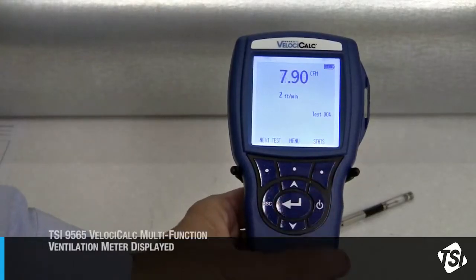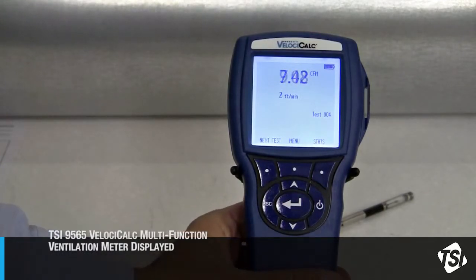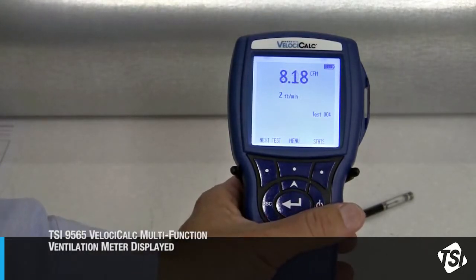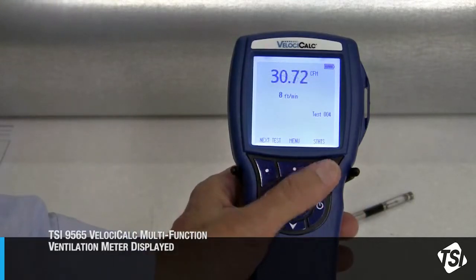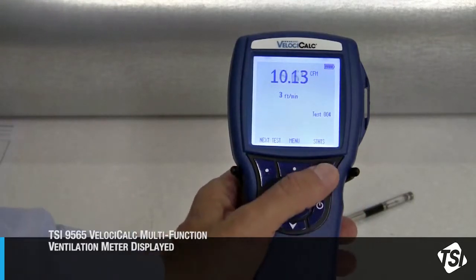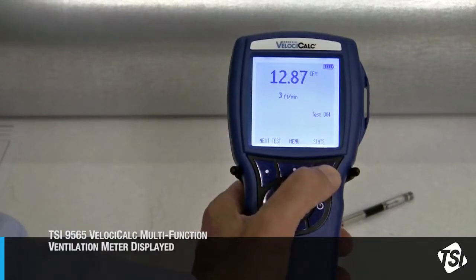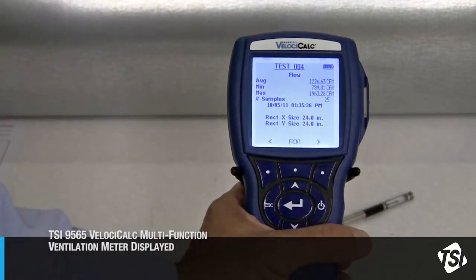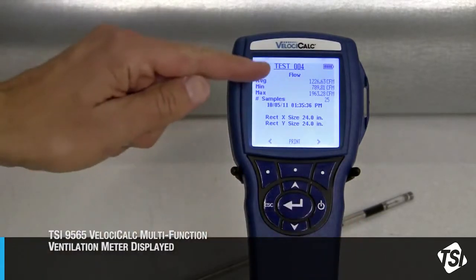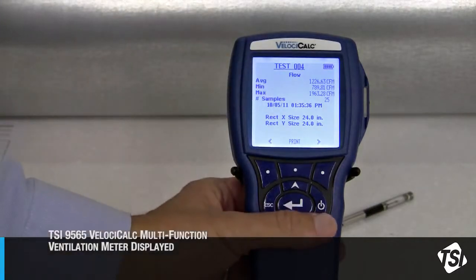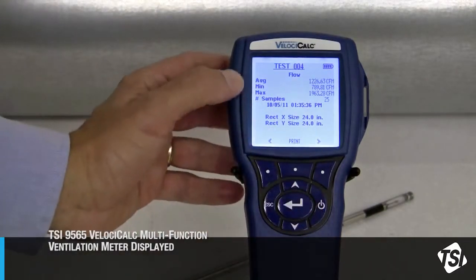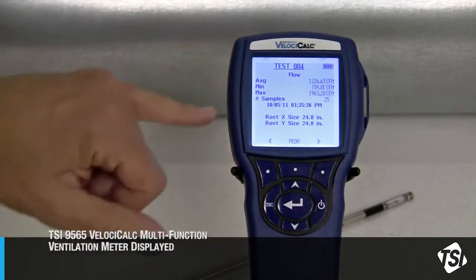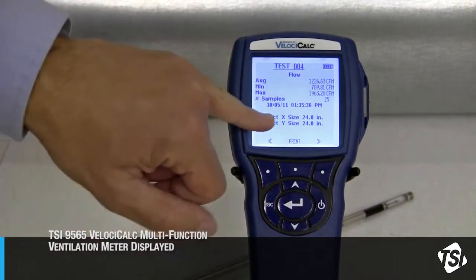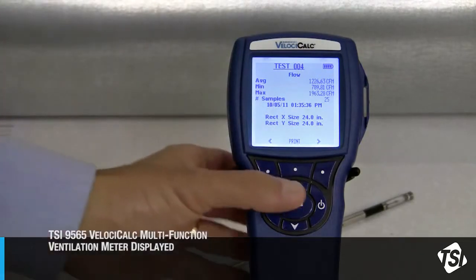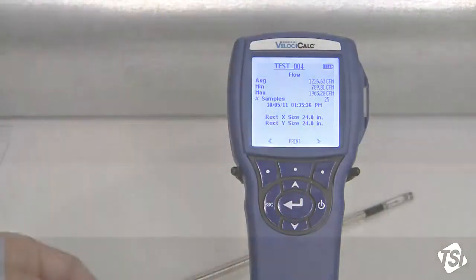After all the points have been measured across the section of the duct, I can review the statistics to find out what the overall average airflow rate was. I can press the right soft key under the stats indicator. I see that the flow is the measurement that I'm looking at. My average is 1226 CFM. My min and max, number of samples, time and date stamp, and my duct size are also displayed. It's also recorded and can be downloaded from the instrument.